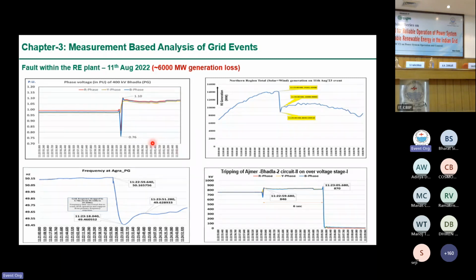This is the plot of solar and wind generation in the northern region. Immediately after the fault clearance, we saw this generation loss of around 6,000 megawatt. And then after 5 to 6 seconds, we also saw some of the evacuating lines going out. So what happened because of which this generation loss took place, and why was this high voltage observed?